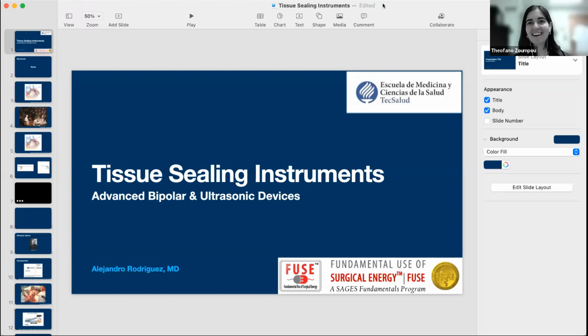If you look back at my study published in Annals of Surgery around 2013 or 14, it's actually about the operating room during lap choles. If you bundle your active electrode cord with the camera cord, electricity goes between the camera cord and the active electrode cord, and you can actually energize the cord of your camera. So you don't want to be bundling your cords in the operating room. But I'm not sure that's the most clinically important one - it's insulation failures and direct application that matter more.